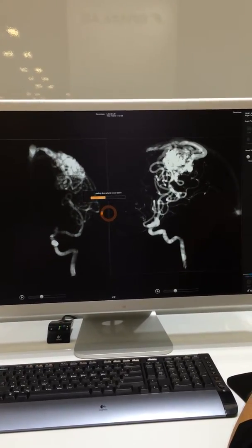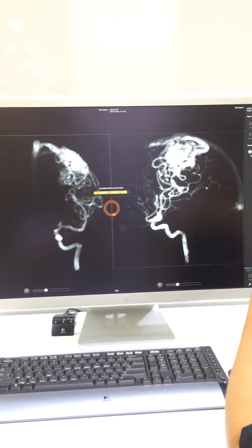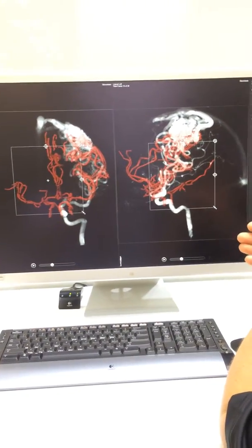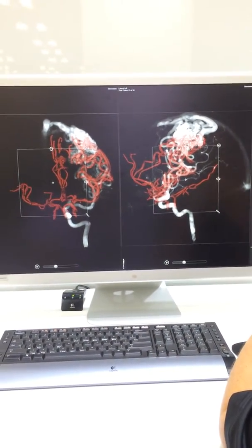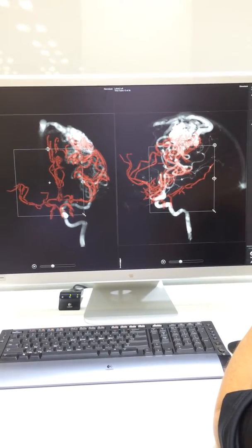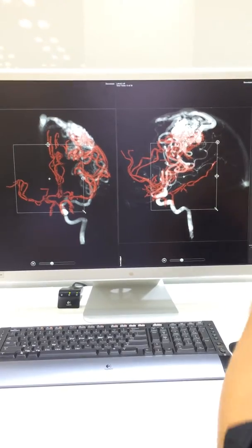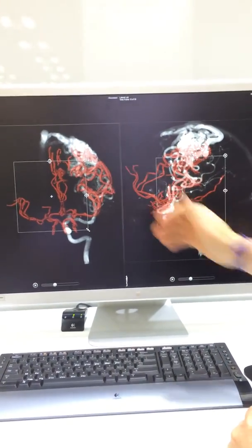So in the past as well, we've always had to have the data sets localized, the 2D planar. This new algorithm is able to do this without a localizer box. We're able to then take images of these DSAs that are done even before the patient comes to radiotherapy, and that allows you to not have the patient go again to get another catheter, another contrast enhancement, and so on. So here we see the DSAs with the 3D vessels.